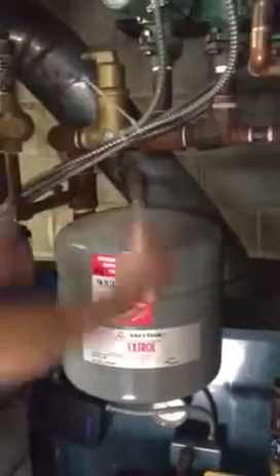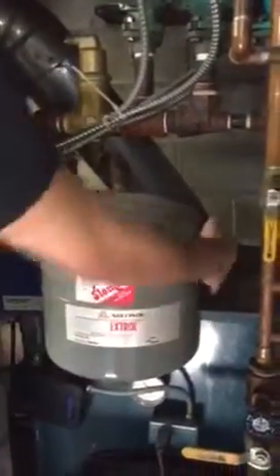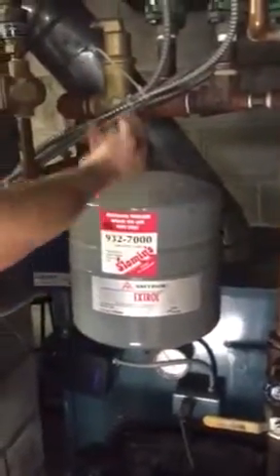Leave the drain valve open when you do this, because it'll break the vacuum. It'll actually allow water to suck back in instead of coming out onto the burner. So leave that open — it'll start pulling what's called a vacuum, it'll suck the water, whatever's left, back into the boiler.